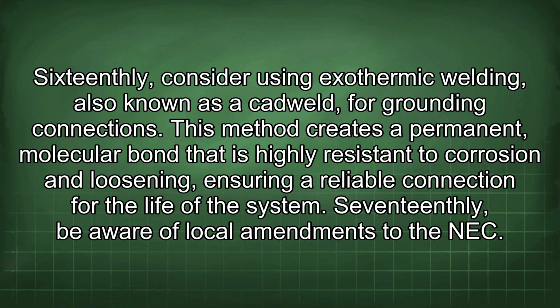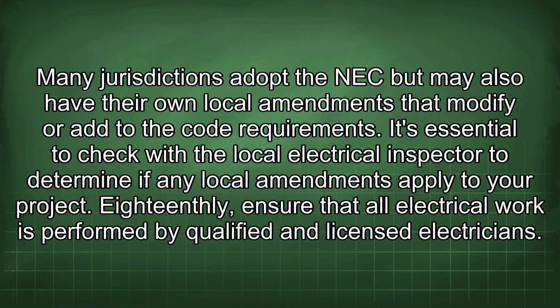16thly, consider using exothermic welding, also known as a Cadweld, for grounding connections. This method creates a permanent molecular bond that is highly resistant to corrosion and loosening, ensuring a reliable connection for the life of the system. 17thly, be aware of local amendments to the NEC. Many jurisdictions adopt the NEC but may also have their own local amendments that modify or add to the code requirement. It's essential to check with the local electrical inspector to determine if any local amendments apply to your project.